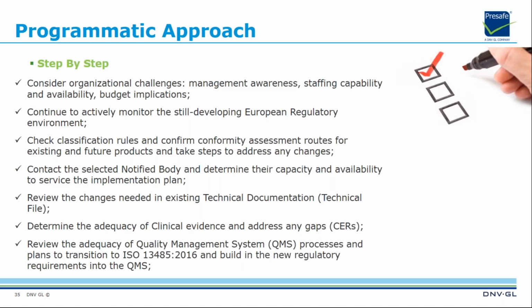Contact the selected notified body and determine their capacity and availability to service the implementation plan. Review the change needed in existing technical documentation, technical file or technical dossier, design dossier. Determine the adequacy of clinical evidence and address any gaps based on clinical evaluation reports. Review the adequacy of quality management system processes and plan to transition to ISO 13485 edition 2016 and build in the new regulatory requirements into the quality management system.